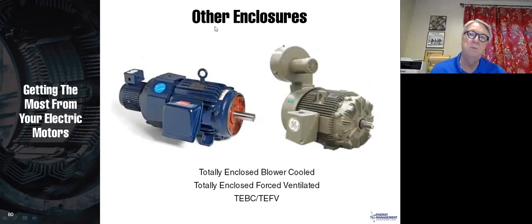This is a totally enclosed blower cooled. We will talk about, and here's two different mountings. I just thought I'd show you both. Sometimes this is called a totally enclosed blower cooled, or could be called a totally enclosed force ventilated fan or motor. And this is a situation where you have it on a drive and you're running it at very slow speeds. Well, when you run a motor at very slow speeds, the fan on the shaft of that motor is not going to provide very much cooling. And so if you need to do that and the motor is going to run at very slow speeds and very high torques, you may need to add a second motor in order to make sure that you have full cooling at all speeds of the motor.